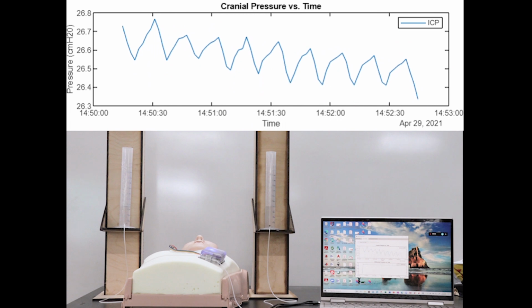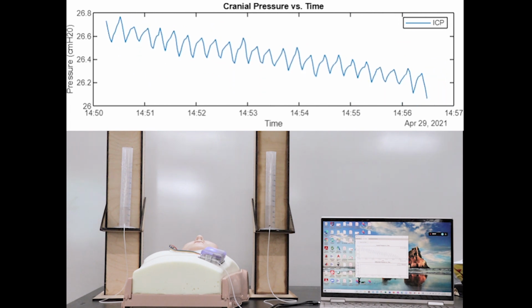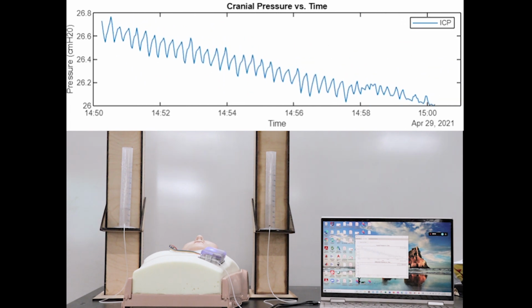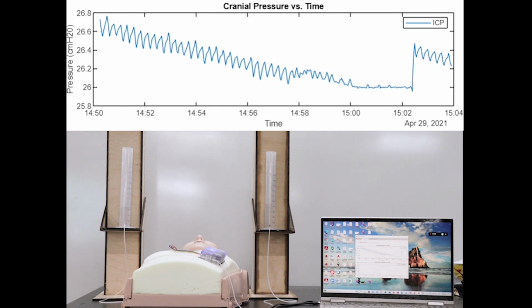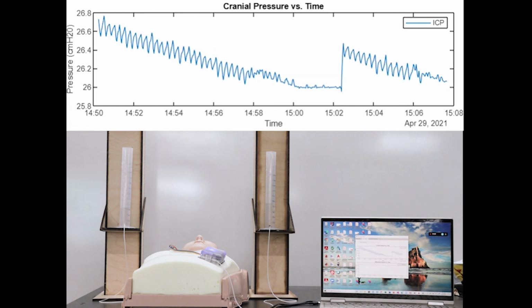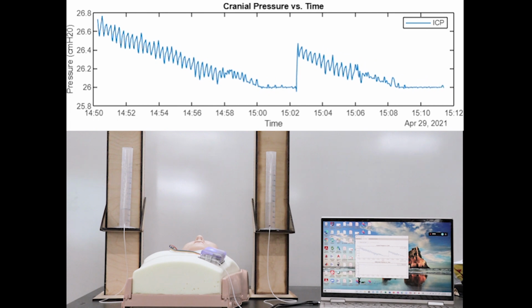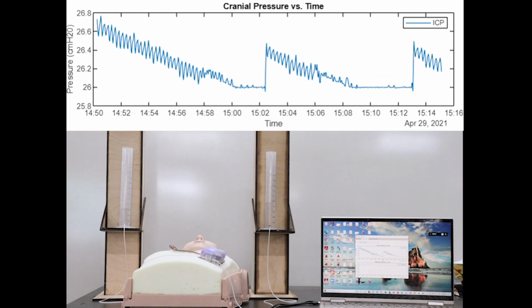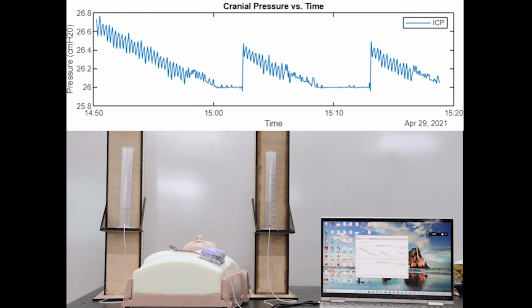Here's a demonstration of the functioning device. In this scenario, the pressure is too high for the patient to tolerate safely. As you can see, the pressure in the head is gradually lowered and eventually stabilized at the target pressure by the device. When water is added again to simulate a subsequent increase in pressure, the pump automatically turns on and stabilizes the pressure once more.